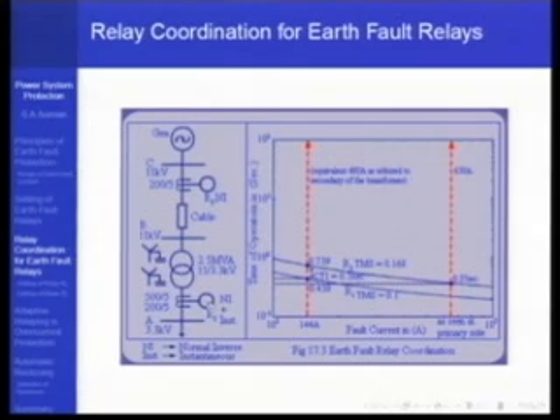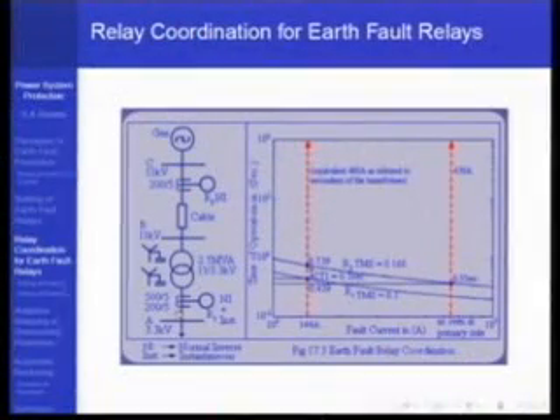Okay, now I want to coordinate. One thing is the setting of the instantaneous relay of R1. That is not a major problem. You look at the fault current, and since there is no backup responsibility for R1 here, you can easily set up the instantaneous element. That's not a major thing. Then there is a normal inverse characteristic that you would set up at 0.1 seconds, for example. There may be something else, maybe a fuse down the line which I have not shown, and therefore normal inverse is more or less straightforward for this particular example. Normal inverse would be set up with a minimum time multiplier setting of 0.1. So that's what you would do.